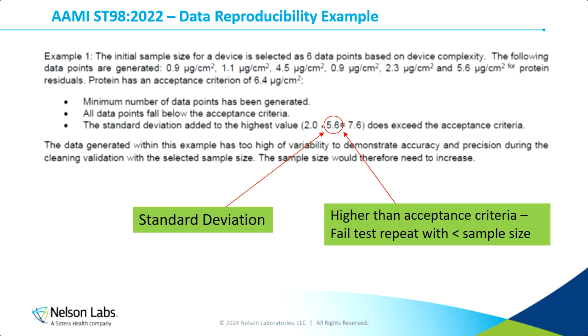So this is an example for data reproducibility. Let's say we have 6 data points for protein. You can see that there are a couple that are higher, that 4.5 and that 5.6, that are still below the acceptance criteria, but they are higher. In this case, we've generated the minimum number of data points, those 6, and all of them are below the acceptance criteria. But when we take the standard deviation and add it to the highest value, that 5.6 result, that exceeds the acceptance criteria. At that point, there is a variability issue. To demonstrate accuracy and precision during the validation, it might be worth either increasing your sample size or, in some cases, adjusting your cleaning procedure to be a little more robust.